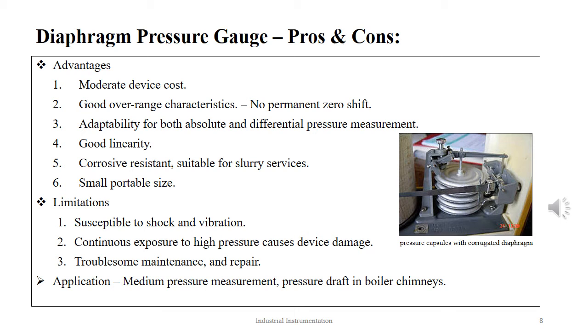The limitations of the diaphragm are that the device is susceptible to both shock and vibration. When continuously exposed to high pressure, it might be damaged permanently. The device maintenance and repair is tedious. Diaphragm gauges find application in medium pressure measurement and pressure draft in boiler chimneys.